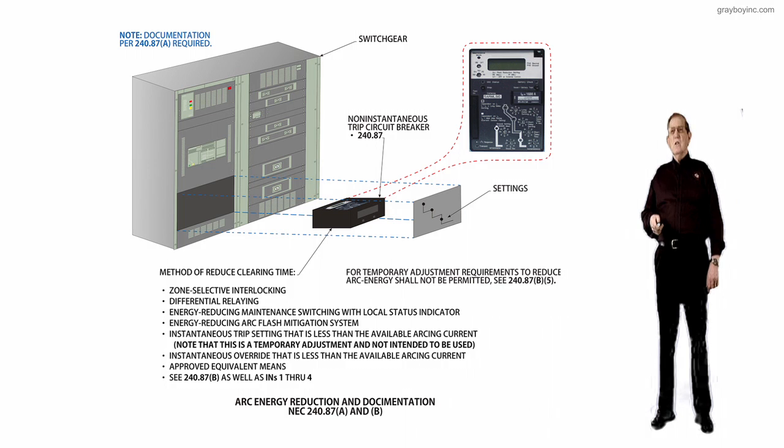This revision clarifies that it is the final setting of the instantaneous trip that determines whether or not an additional arc reduction technique or techniques are required.